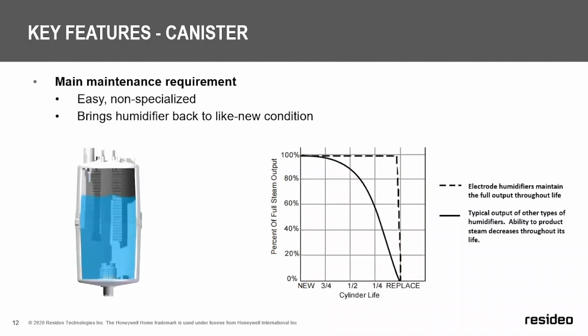The competition actually has the entire cylinder full of water, and that means that on day one, when the cylinder is new, you are slowly consuming the entire cylinder. So your output when new is going to be at 100%, and as the life of that cylinder starts to grow, you will have reduced output. So you can see at half life, your output is roughly 60% in that design, meaning that your 11 gallon per day output is really giving you something closer to 6 to 7 gallons per day. That could be a problem in a home that needs 11 gallons per day. So one of the main benefits to the Resideo design of the HM750 is that full output from beginning of life to replacement.